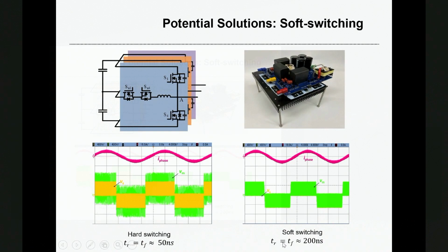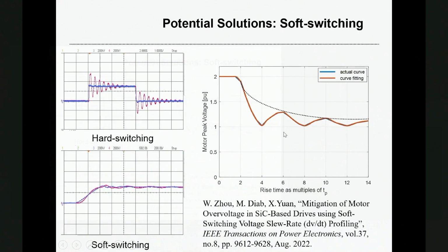So basically, how to set the rising or falling time of the soft switching converter. If you set the rise time of the soft switching converter output voltage to be 4 times the traveling wave time along the cable, then you can eliminate the voltage overshoot. And at other times, for example 8 times the traveling time along the cable, you can also remove the terminal over voltage.